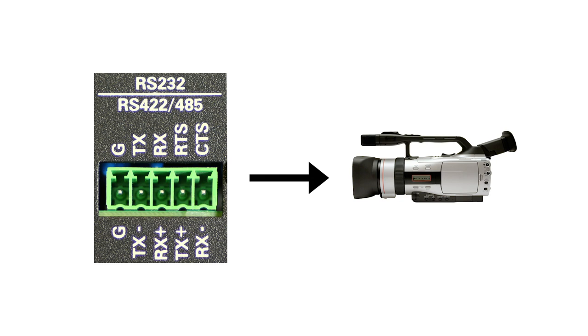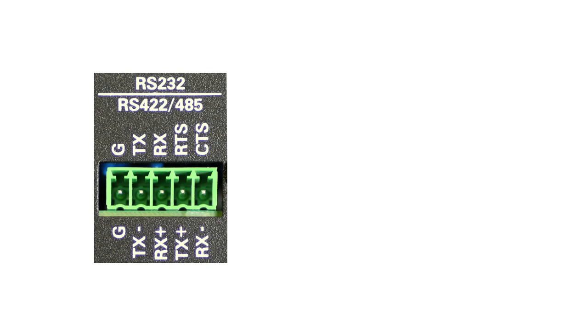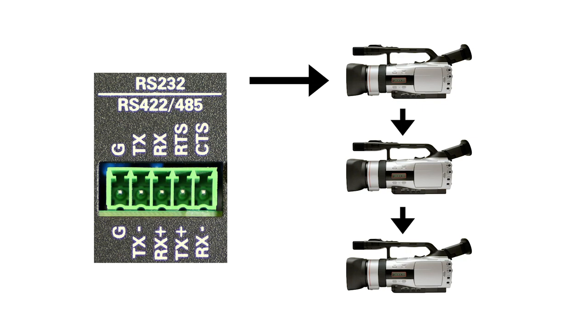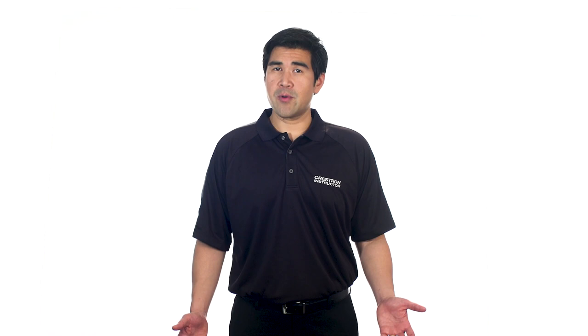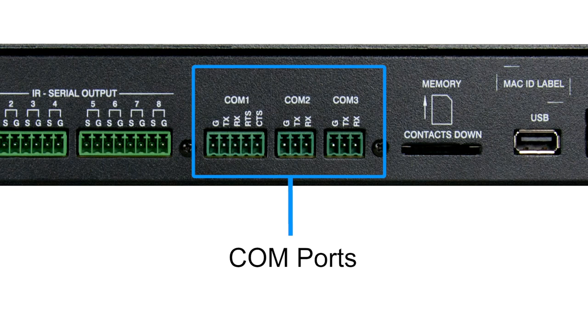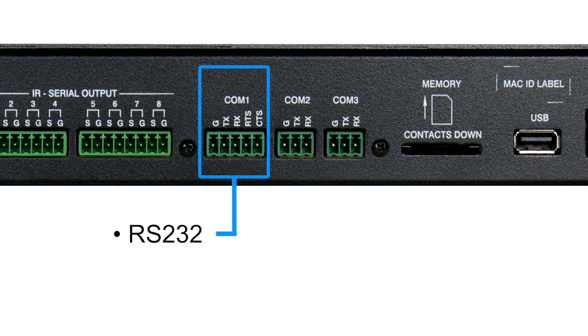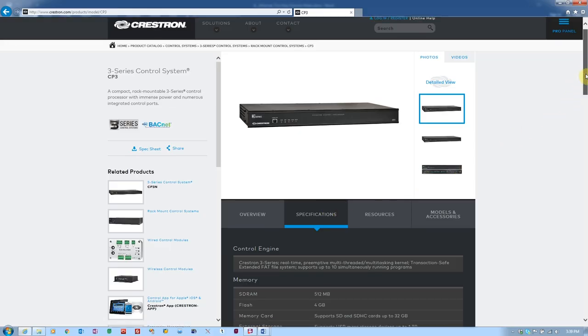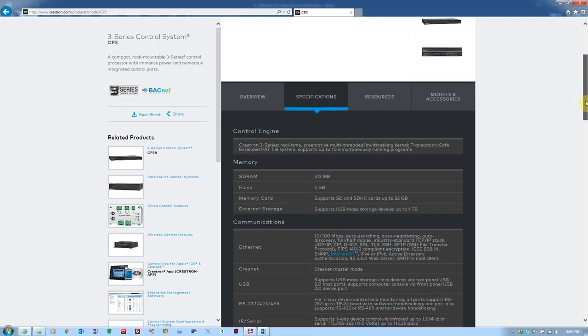RS-422 is less common but still in use because it is a balanced communication that offers greater distance over RS-232. RS-485, like RS-422, is also a balanced communication, meaning it is less susceptible to external influences such as electrical interference or RF noise. An advantage of RS-485 is that it can do multipoint communication, meaning many devices can be placed on the same network. Not all ports support RS-422 or RS-485. On the CP3, there are three COM ports: the first supports RS-232, RS-422, and RS-485, while the other two are RS-232 only.